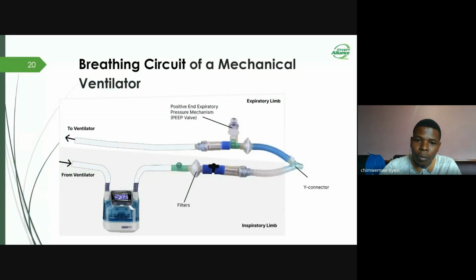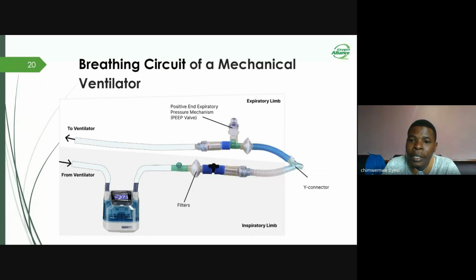So the breathing circuit of a mechanical ventilator comprises two main limbs. We have the inspiratory limb and also the expiratory limb. You can see in the graphics the part that has shades of gray, that's the inspiratory limb, and the one that's in white is the expiratory limb. So the inspiratory limb is responsible for delivering fresh gas from the ventilator to the patient's lungs during the inspiratory phase. It typically contains a Y-piece. So the Y-piece is a component that directs the flow of gas towards the patient. Connected to the inspiratory limb is also an inspiratory valve, which controls the opening and closing of the limb during the breathing cycle.